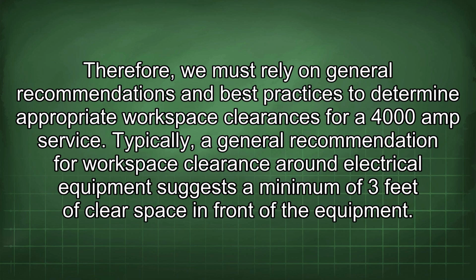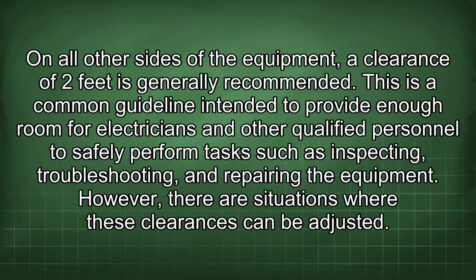Typically, a general recommendation for workspace clearance around electrical equipment suggests a minimum of 3 feet of clear space in front of the equipment. On all other sides of the equipment, a clearance of 2 feet is generally recommended. This is a common guideline intended to provide enough room for electricians and other qualified personnel to safely perform tasks such as inspecting, troubleshooting, and repairing the equipment.